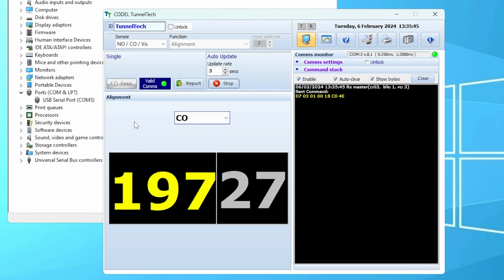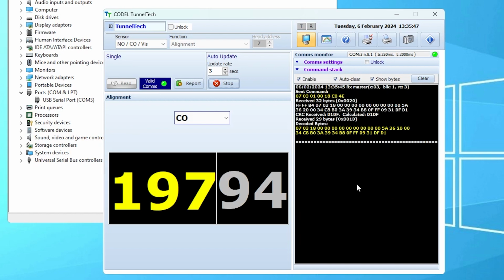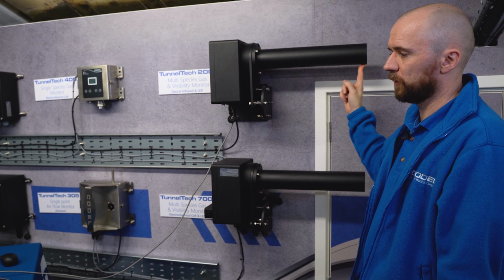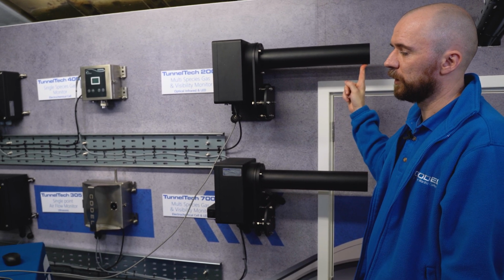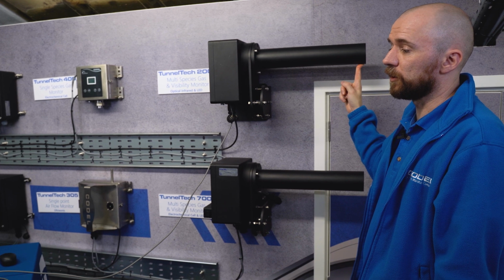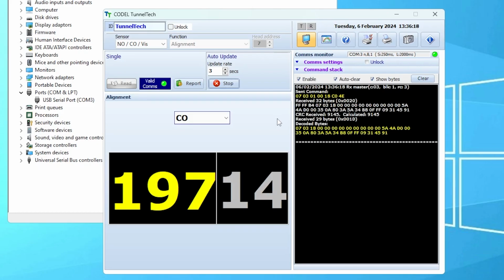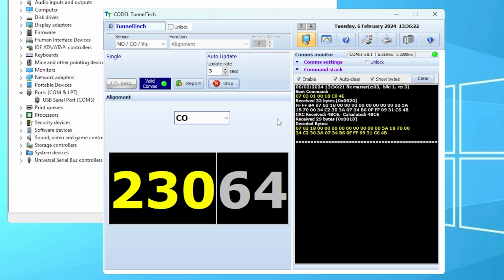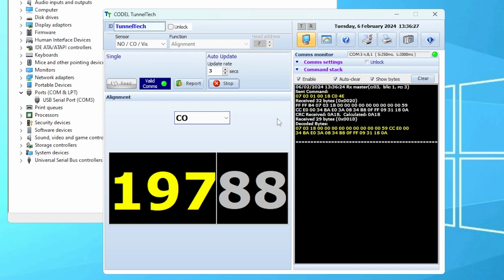When making the fine adjustment, to first gain an understanding of which direction to push the alignment in, you can use a small, what we call a push test on the tube. So if you put a small amount of pressure in one direction and then observe the detector levels, if they increase, that's the way you want to align the system to. Letting go of the tube should allow the detector level to reorientate and drop back down.